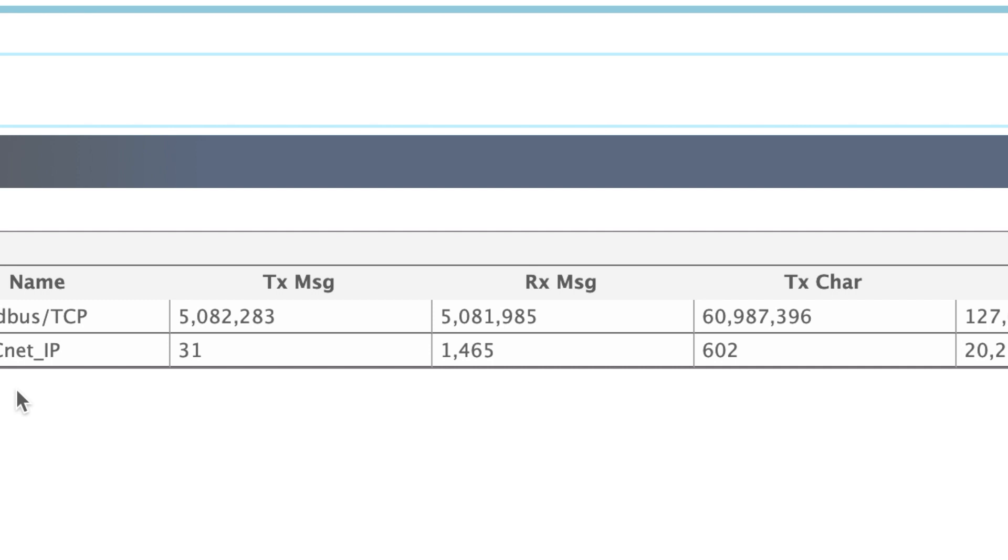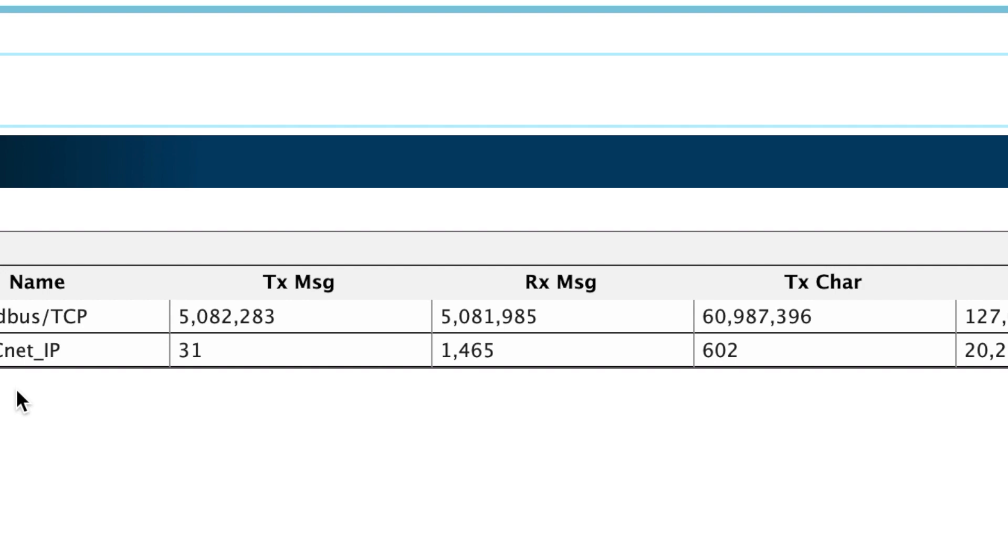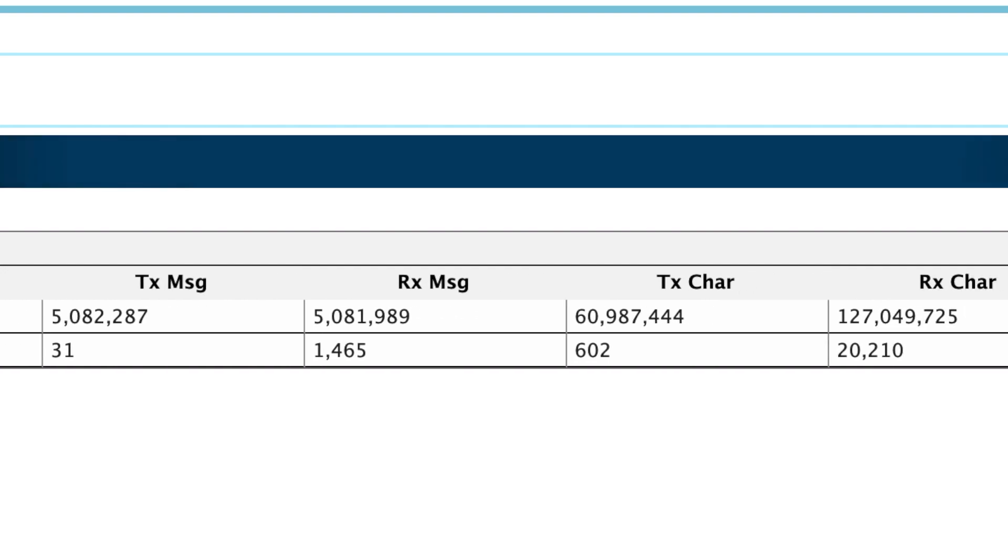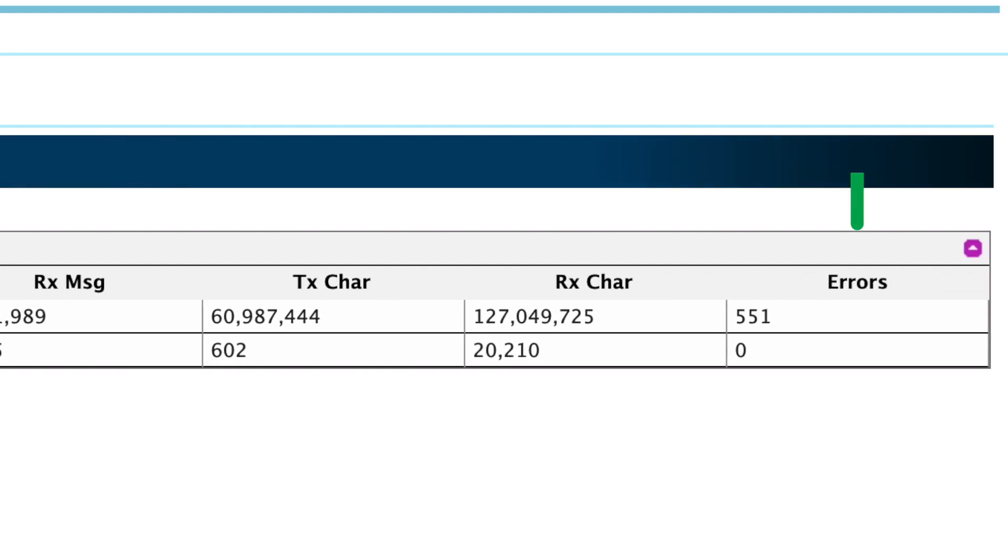If you do not see the TxMessage and RxMessage columns incrementing, or if you see errors incrementing under the Error column on the right-hand side, you will need to contact the technical support of your OEM vendor of the Protonode for additional support.